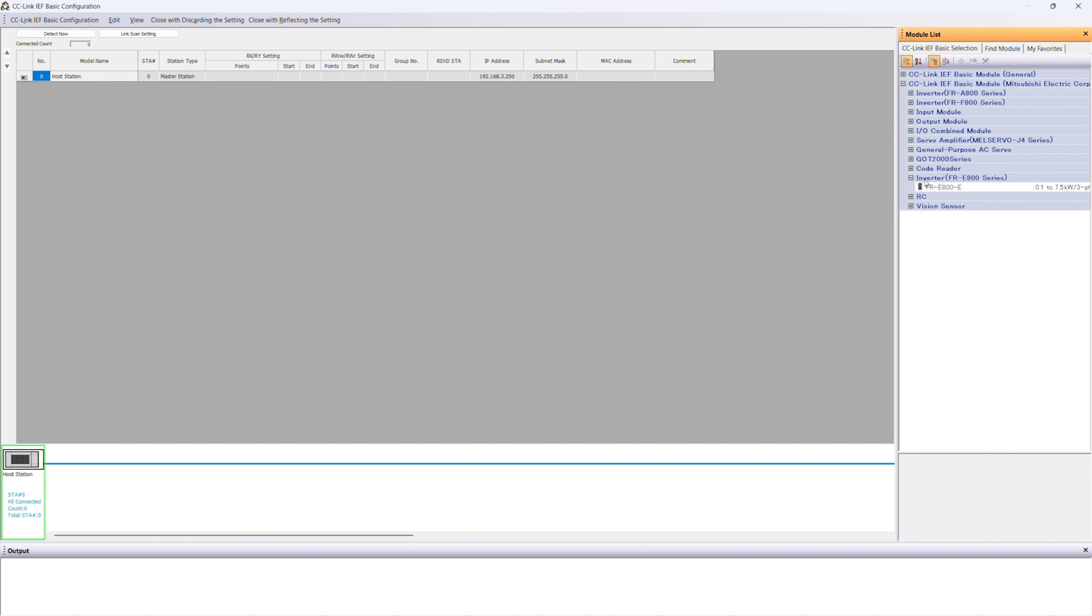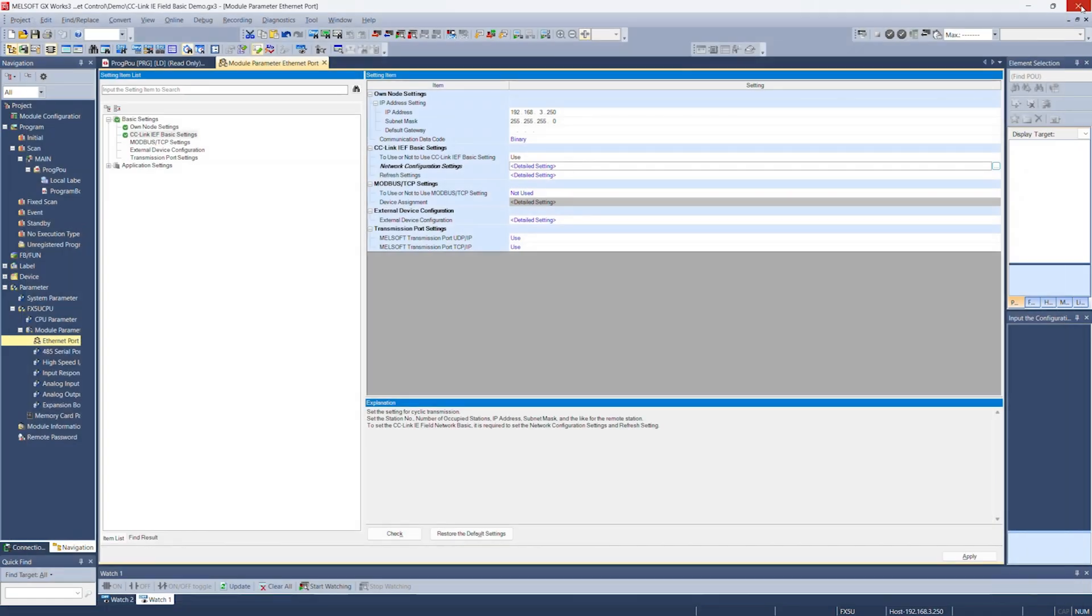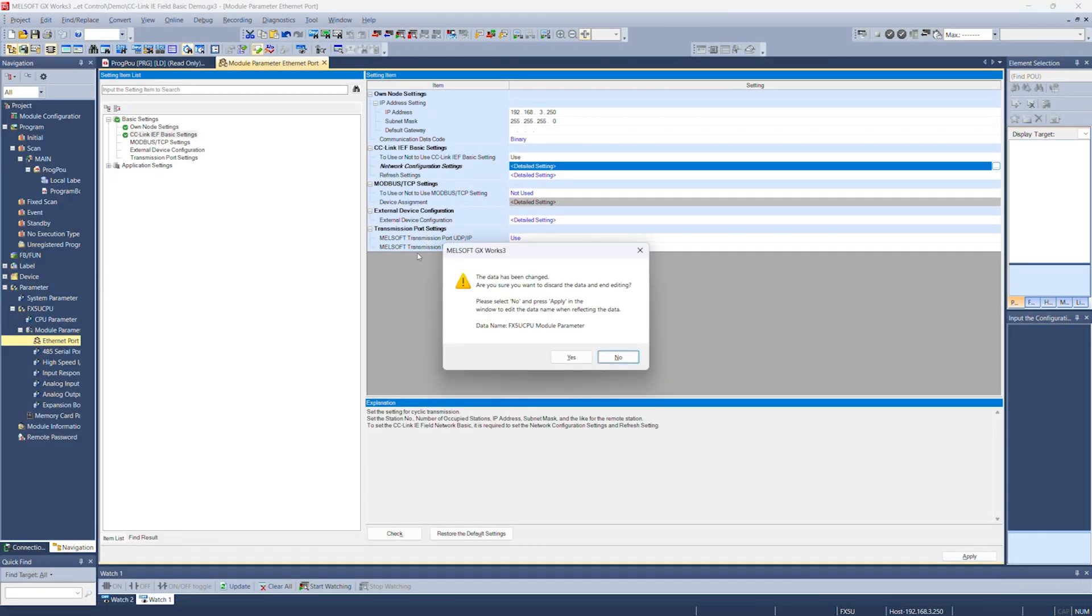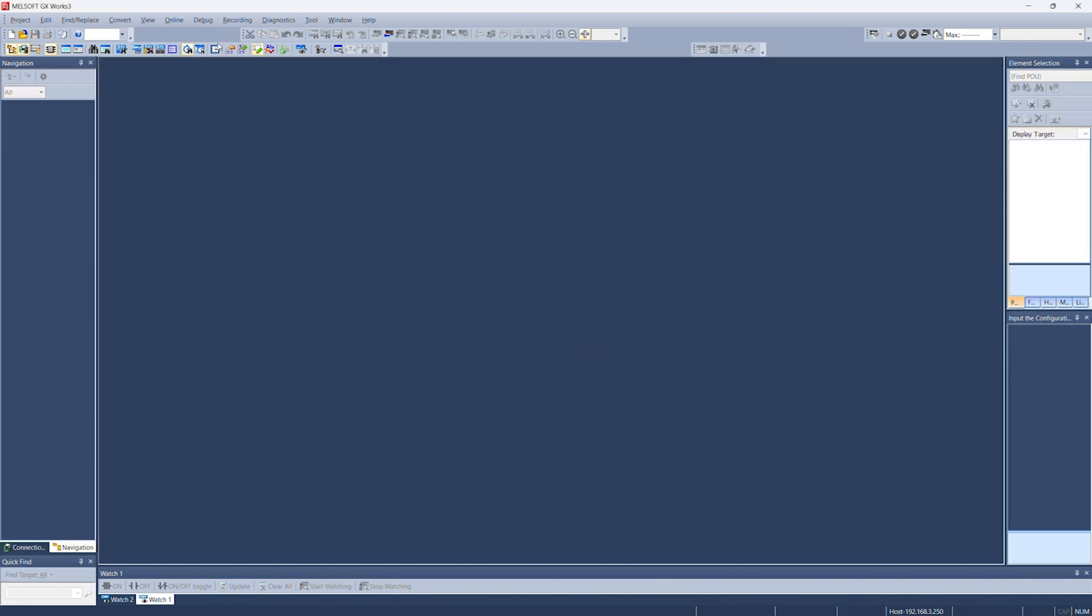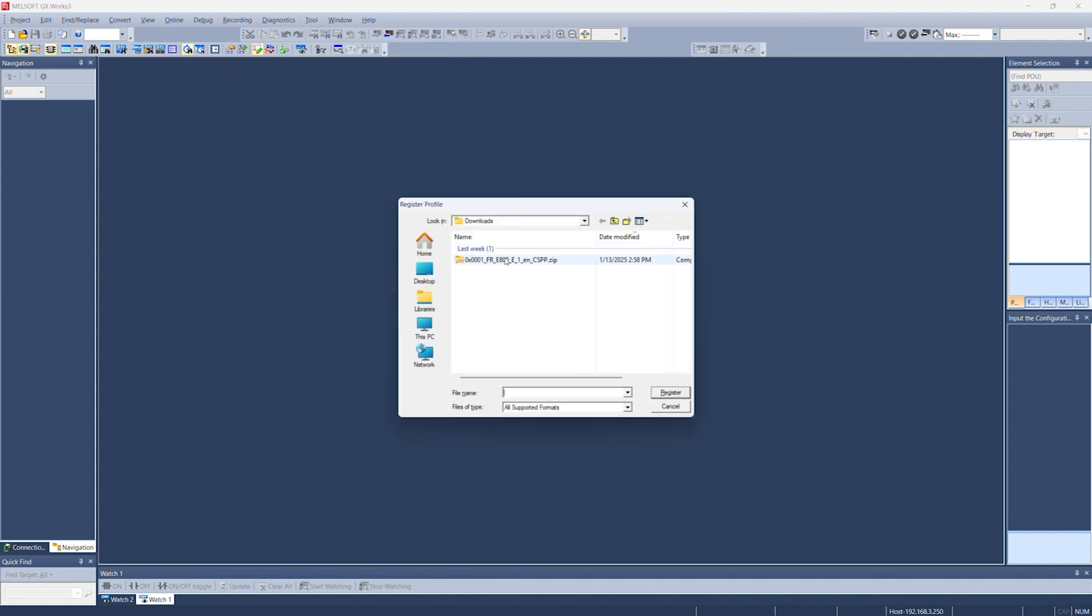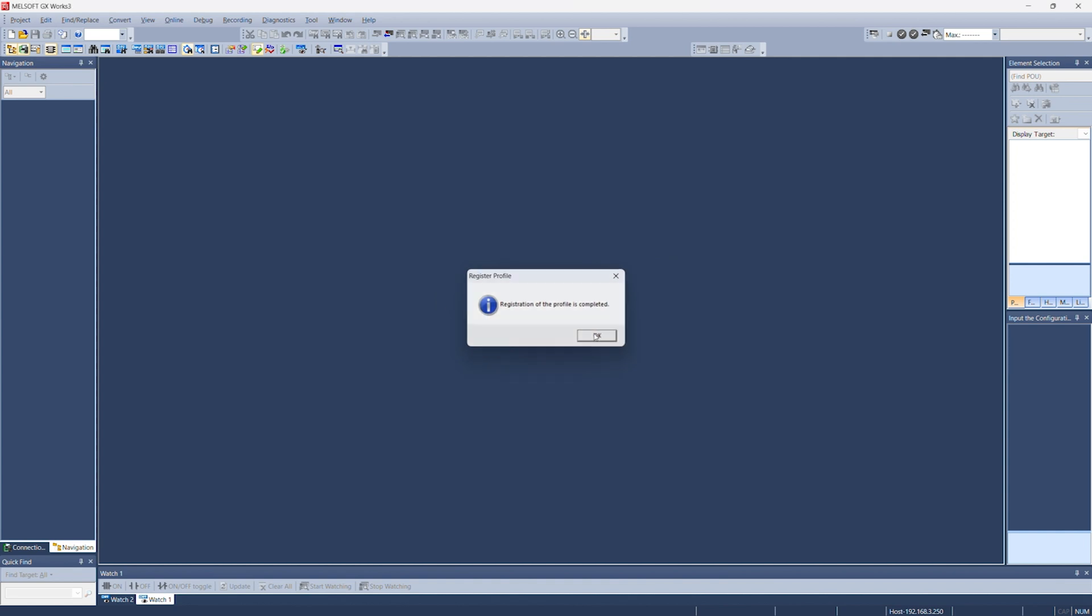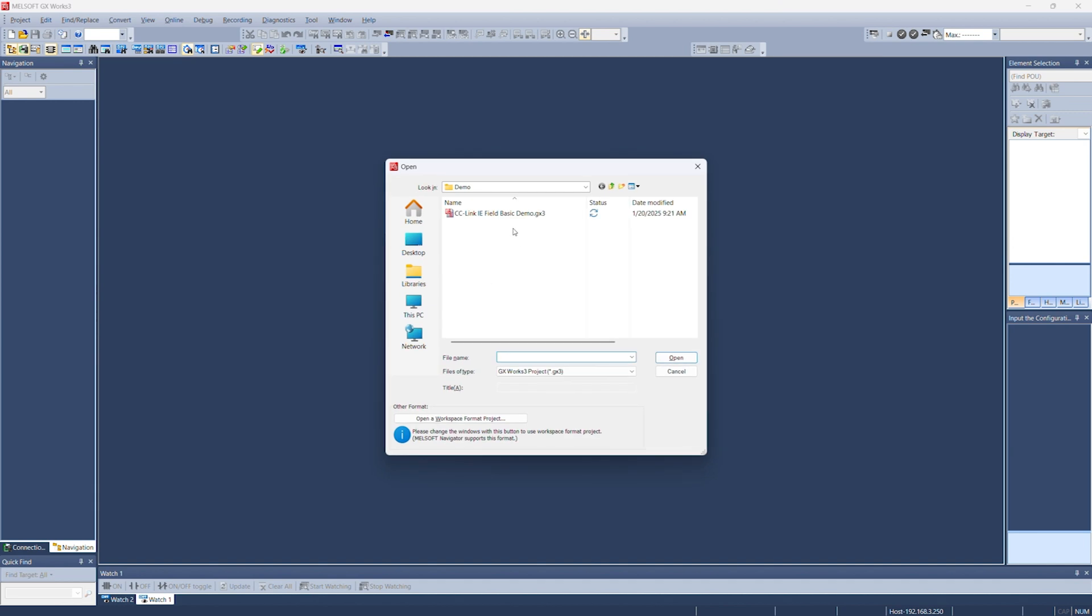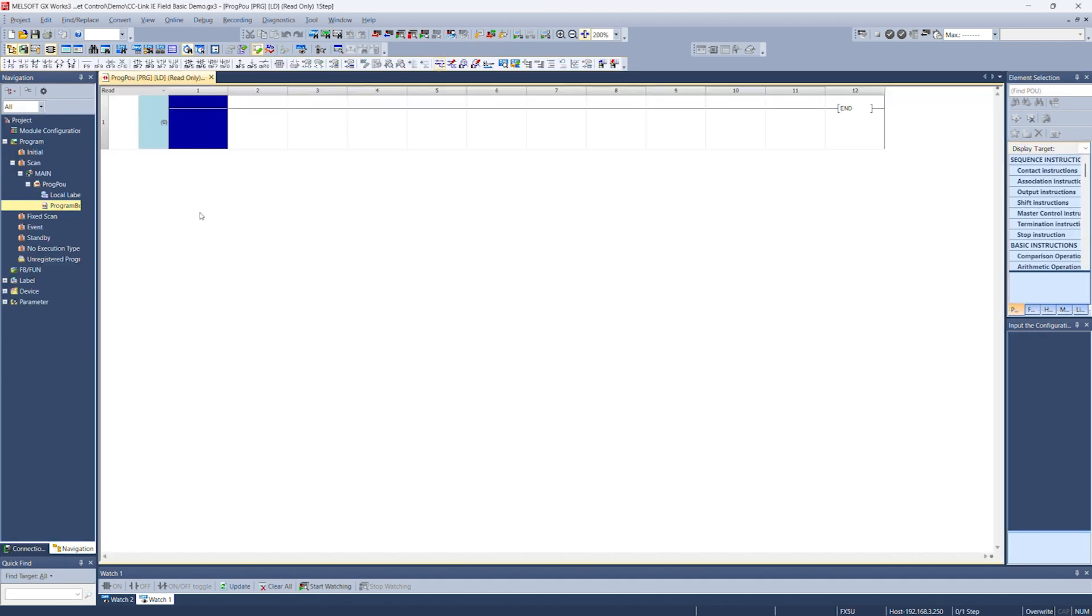If you do not see in your module list on the right the FR-E800 inverter, then you'll need to register the inverter's profile. To do that, you're going to close your project, go to tool, profile management, register. Now you'll need to download this CSPP file for the FR-E800 inverter. You can find this online and we'll post a link to it as well. Register the profile. It'll tell you it's complete. And now we can get back into our project.